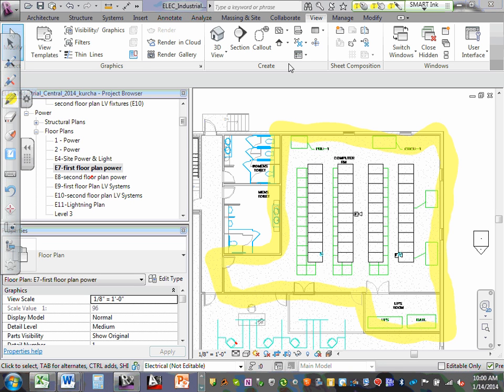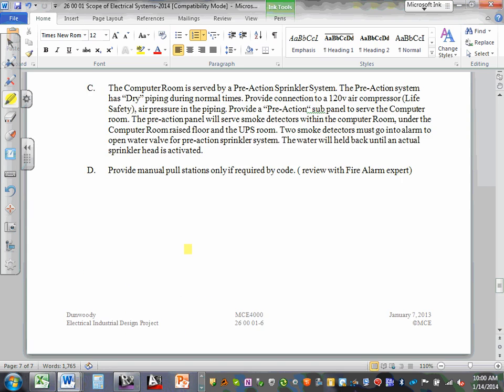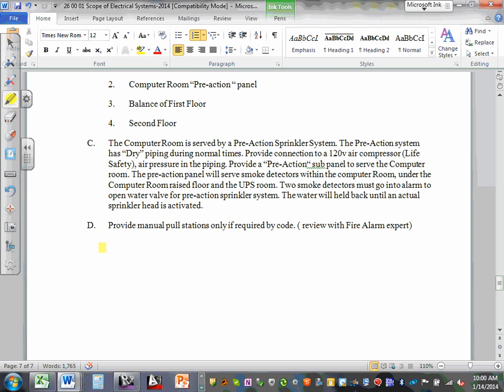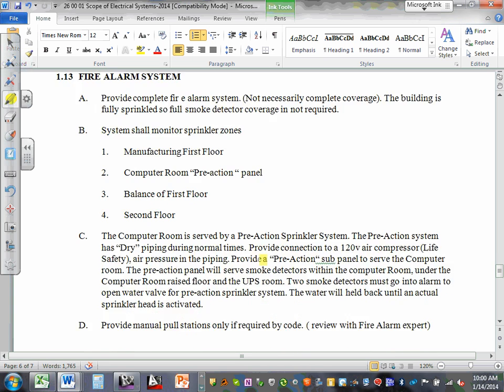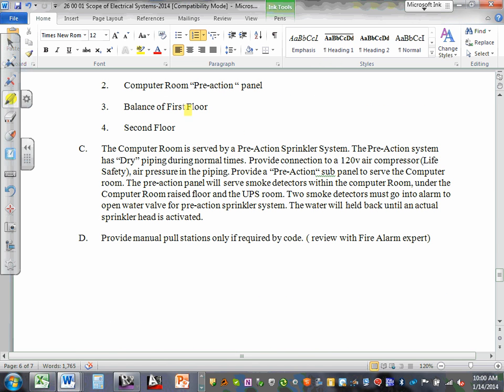A pre-action sprinkler system is one in which the pipe is empty. There's no water in the pipe. It starts from a valve assembly where the water is held back. That pipe leaves the valve assembly and goes out to the sprinkler heads within the protected area. Let's say that this room here is the data center, and we've got sprinkler heads on the ceiling in this room, but there's no water in the pipe.